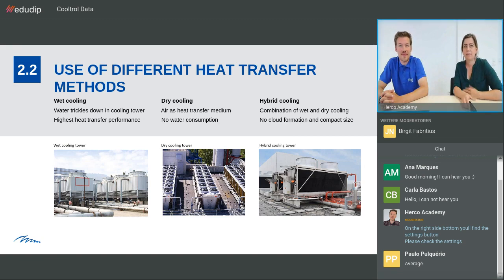Good. Well, there are different heat transfer methods as well. So there's the wet cooling tower, which pretty much corresponds to the open circuit that we have talked about right now. Water trickles down in the cooling tower. It has the highest performance, as we said, but it has a lot of contact with air, with all the consequences. There is also dry cooling. That means it is really only air as a heat transfer medium. So water is not consumed. We have water only in the internal circuit, but water is not evaporated.